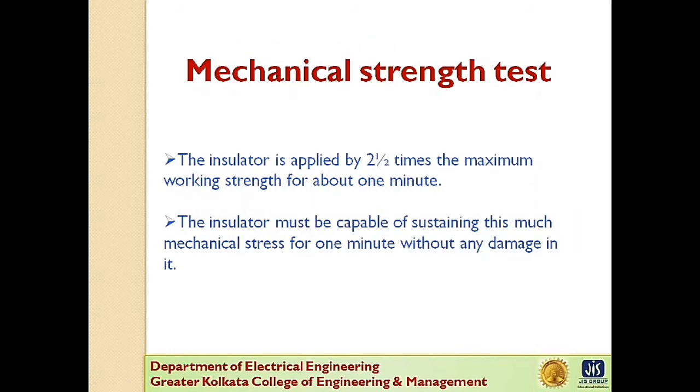Next one is the mechanical strength test. In this test, the insulator under test is loaded by 250%, that means 2.5 times of the maximum working load for 1 minute.